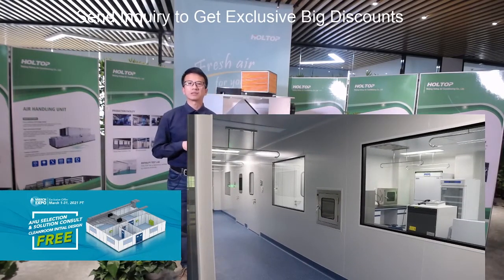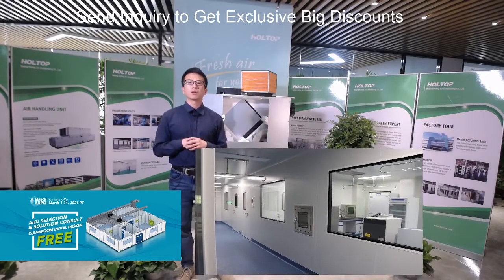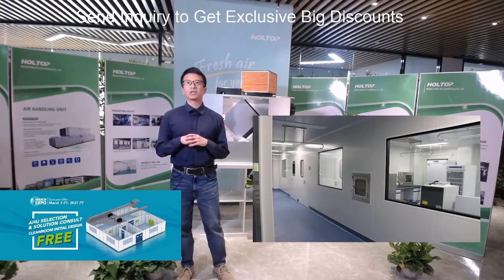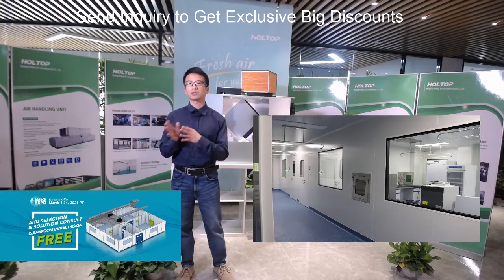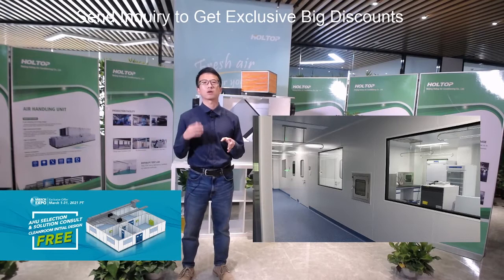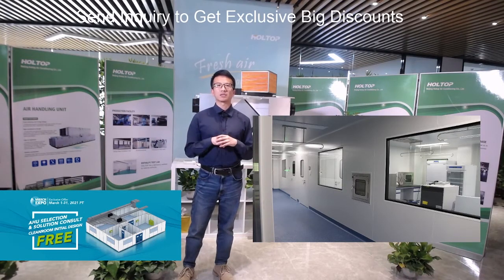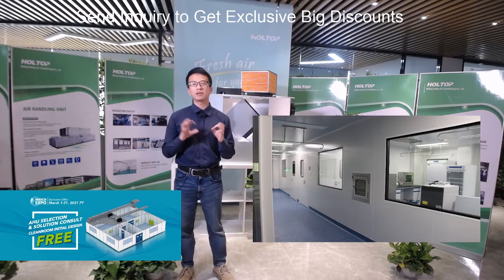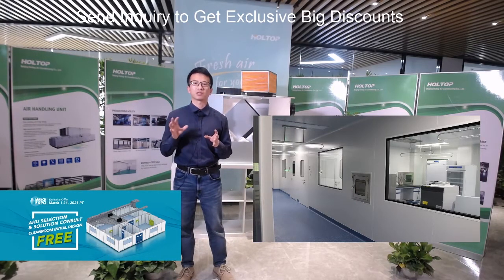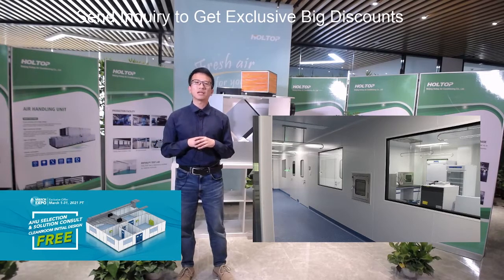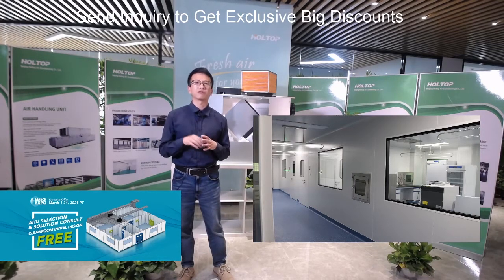From the first picture, you can see the construction of the corridor. When you look at it, you can see two windows looking inside the amplification room. And there is a pass box on the wall. That is for medical people to transfer the products from the corridor into the room that we just talked about a while ago. And on top of the ceiling, you can see those U-shaped mini lamps. That is the UV lamp for sterilization. Every day, the light has to be on for about 30 minutes to sterilize the bacteria and virus in the air. Okay, so let's move to the next picture.